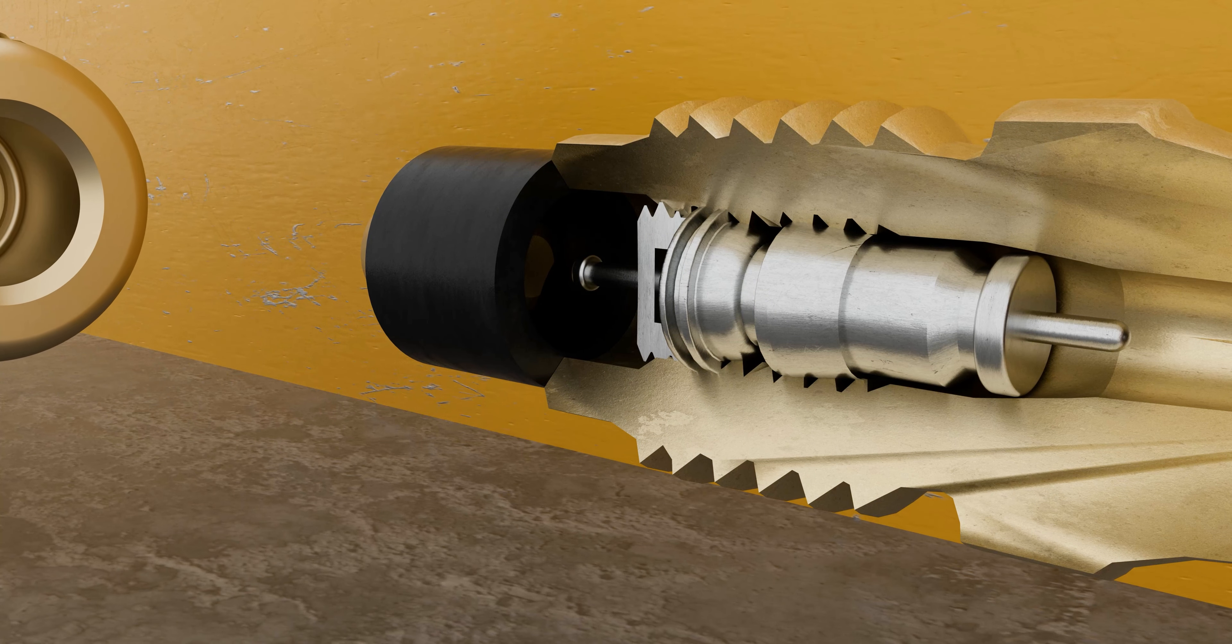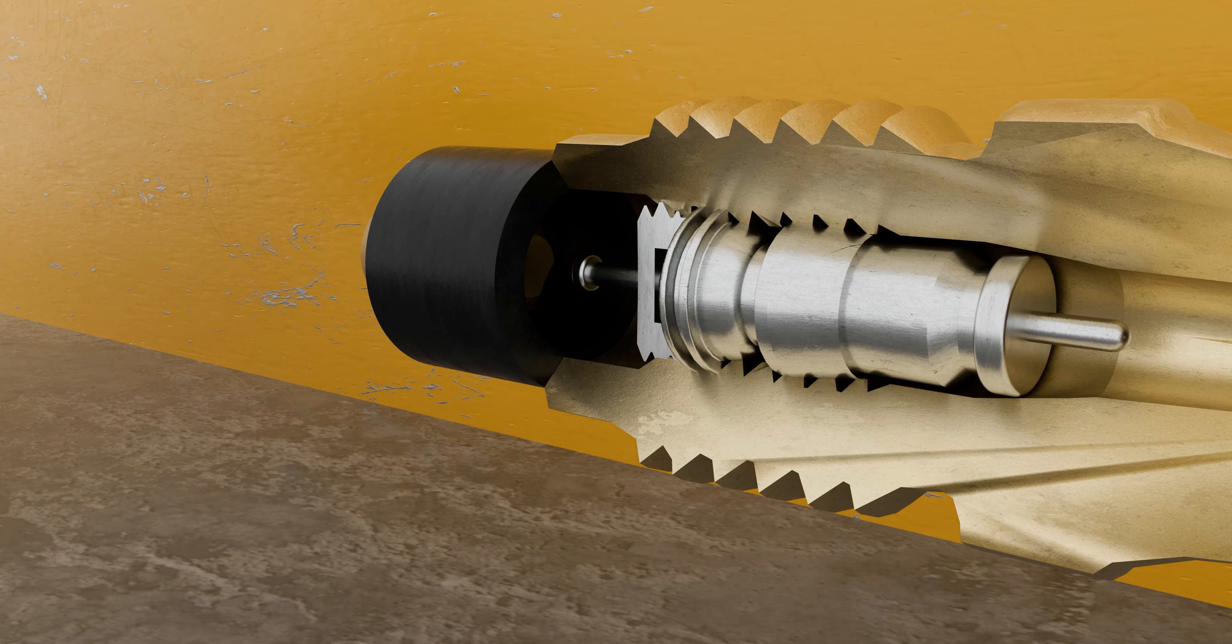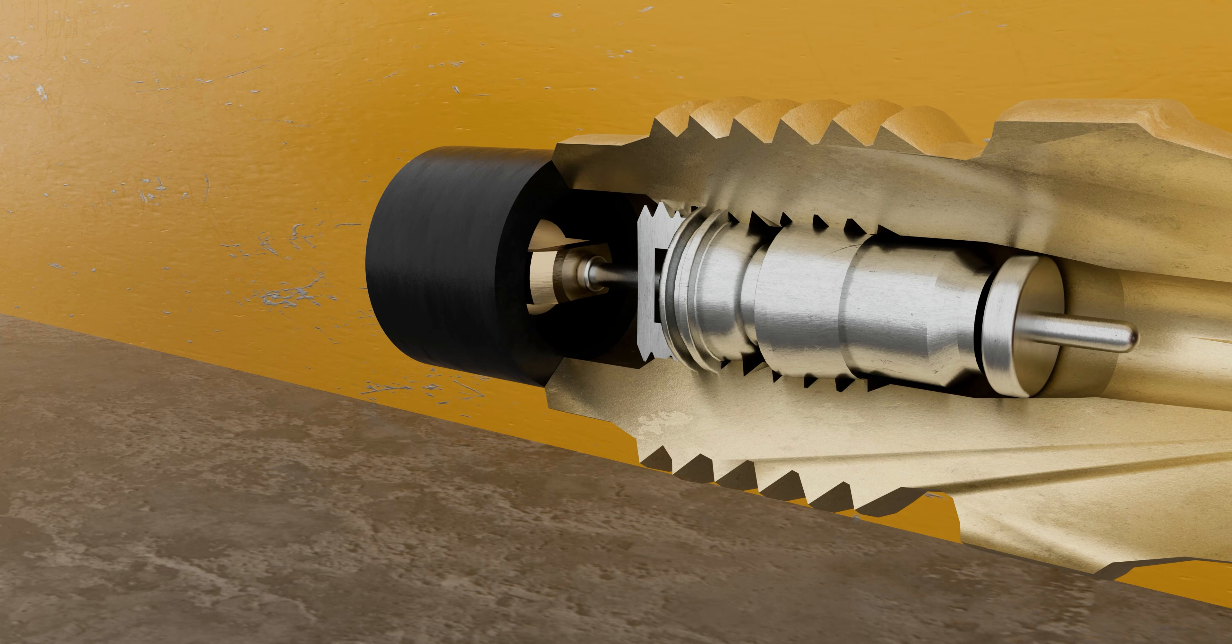It's important to always set the core depressor as deep as possible, then slowly and incrementally adjust the depressor until it begins to make contact with the valve core.